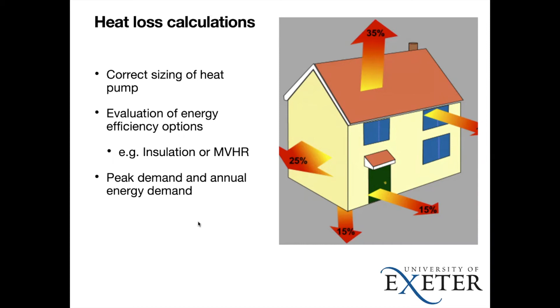Also looking at highlighting both the peak demand, the size, the rating of the heat pump, but to properly size the ground array, understand the annual energy demand. We got some properties that we looked at which were largely used for hot water in the summer, needed a relatively small heat pump, but quite a draw through the summer months for water heating. Other sites, like the building here, which was supposedly initially going to be topped up with a gas boiler, but would have meant the heat pump was running at a much higher duty, the initial heat pump. So the ground array would be a relatively large demand compared to the rating of the heat pump.